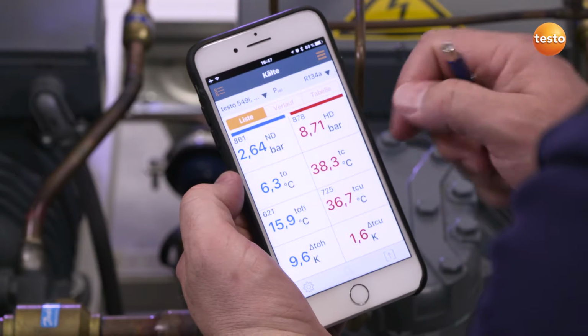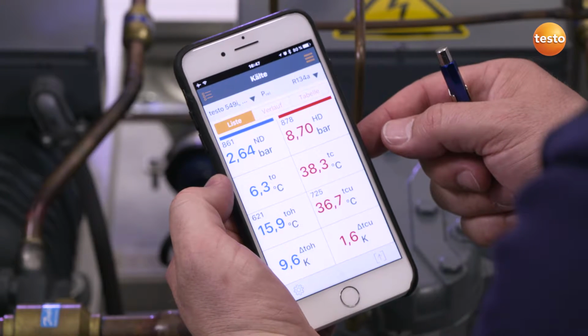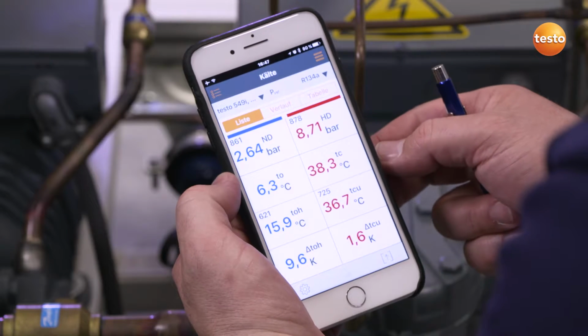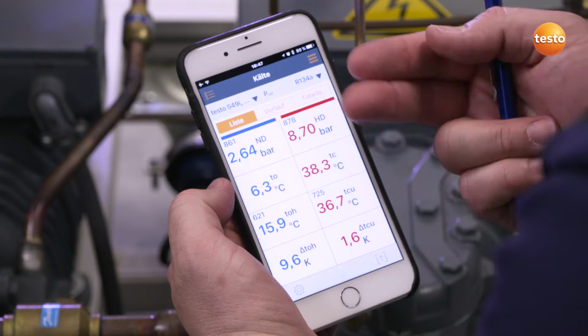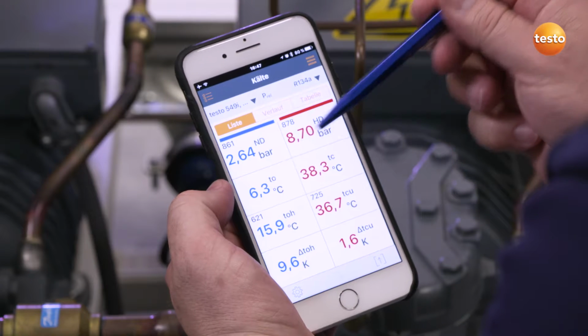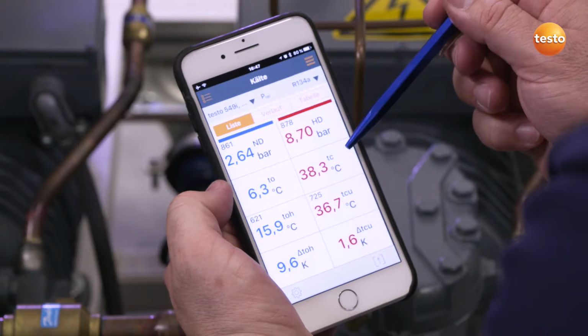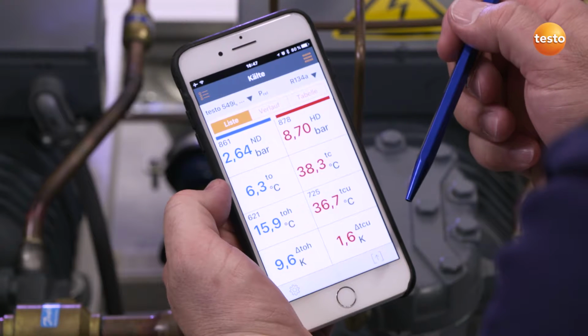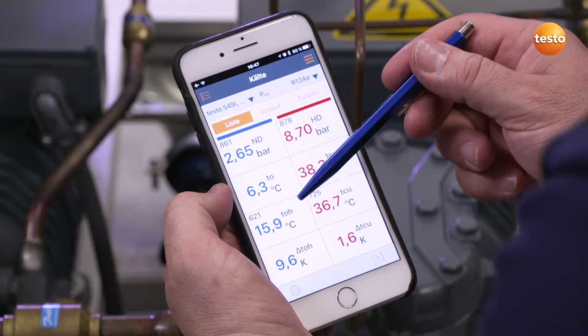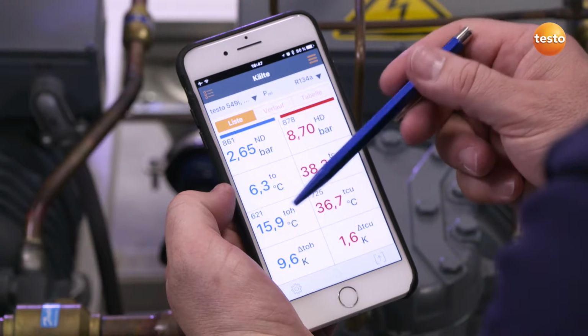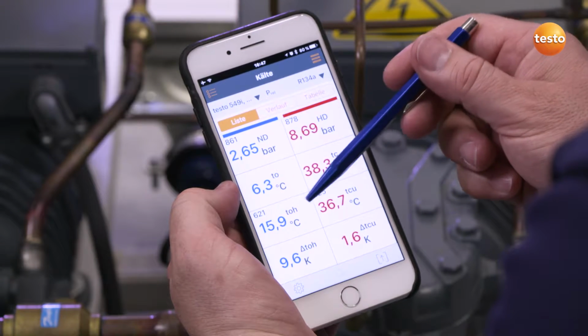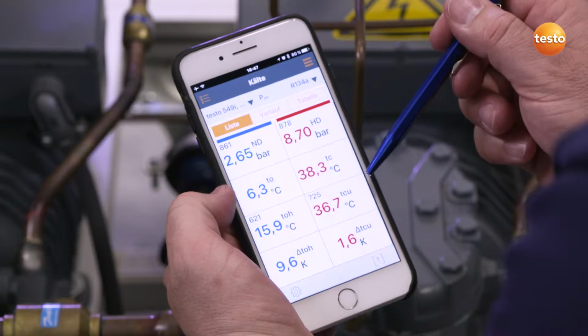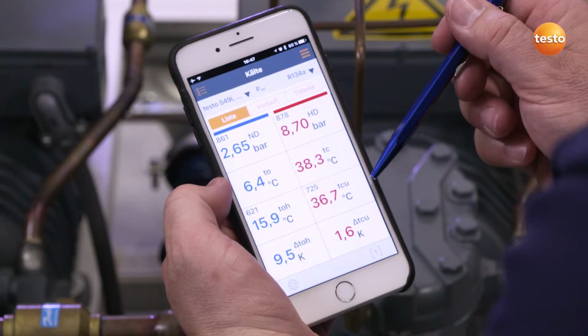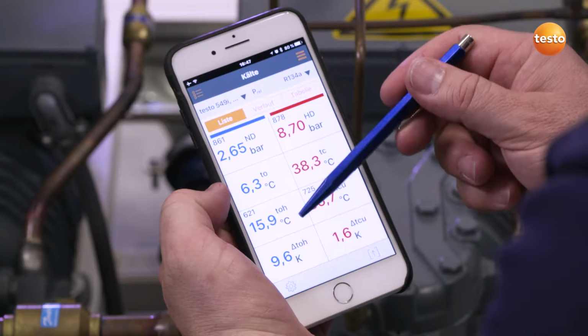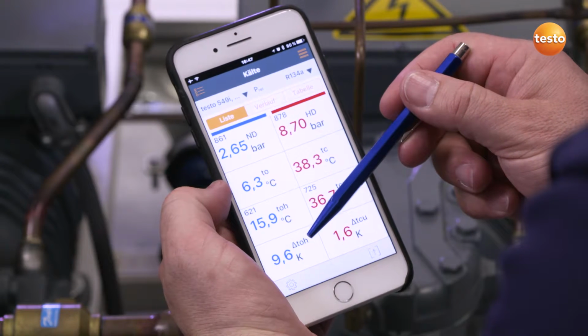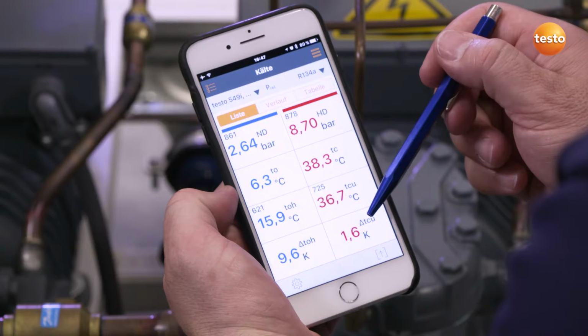The high-pressure probe reports a pressure of 8.7 bar. The low-pressure probe, 2.6 bar. The instrument automatically converts the respective evaporation and condensation temperatures, which we are then able to read directly. Both temperature probes report a temperature of 15.9 degrees Celsius at the evaporator outlet and 36.7 degrees Celsius in the liquid line. The corresponding evaporator superheating is also generated here automatically. In our case, 9.6 Kelvin is indicated and a subcooling of the liquid line of 1.6 Kelvin.